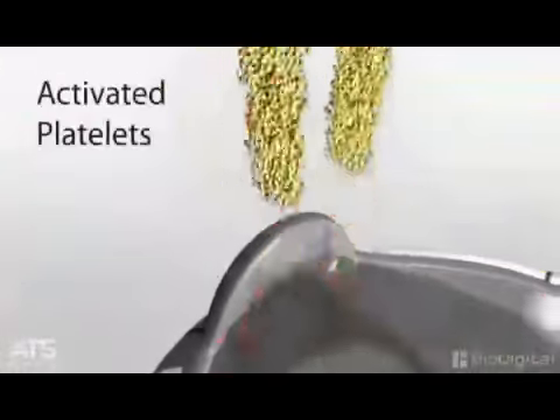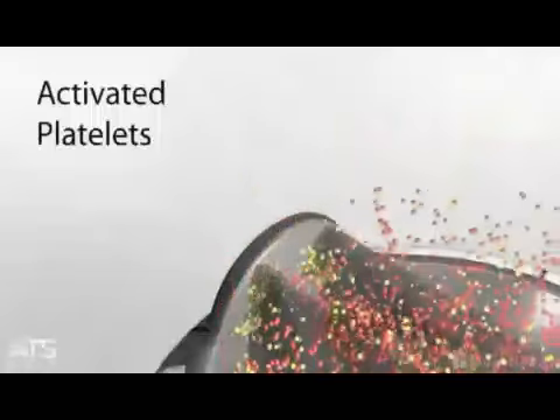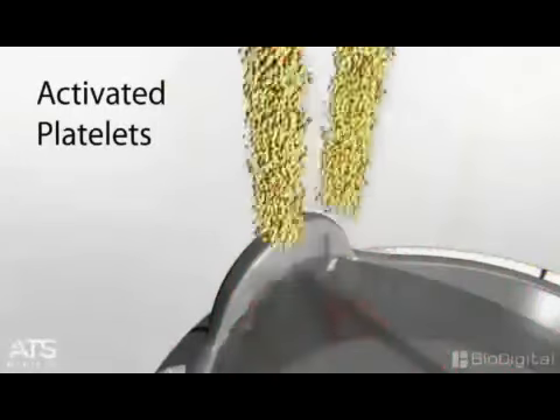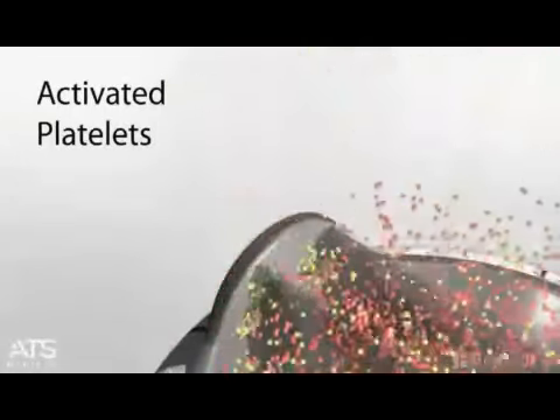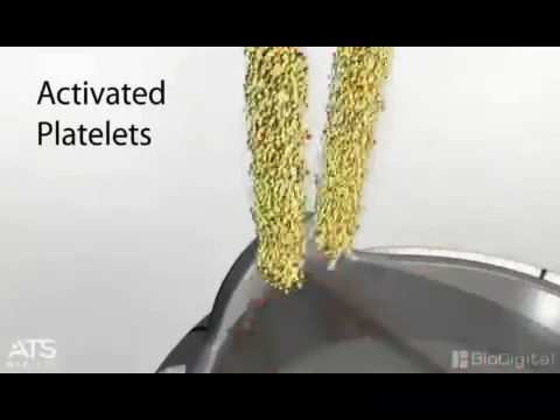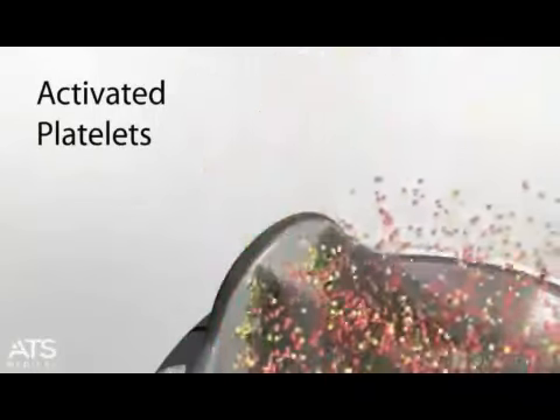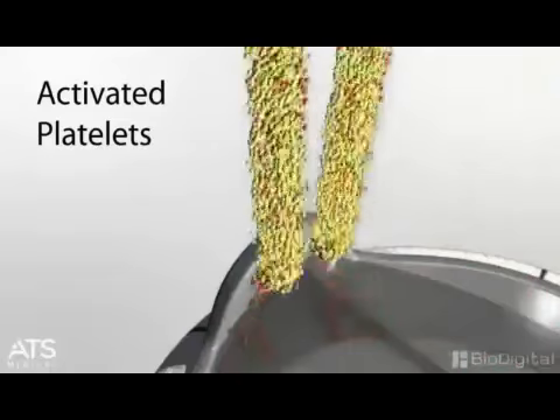Studies have shown that, compared to the flow through the open pivot valve, cavity pivot valves result in higher shear stress. Regurgitant jets used to wash the cavity pivots are high velocity, cause high shear stress, and create more turbulence. This activates some of the platelets and is believed to be the major cause of mechanical valve thrombogenicity.